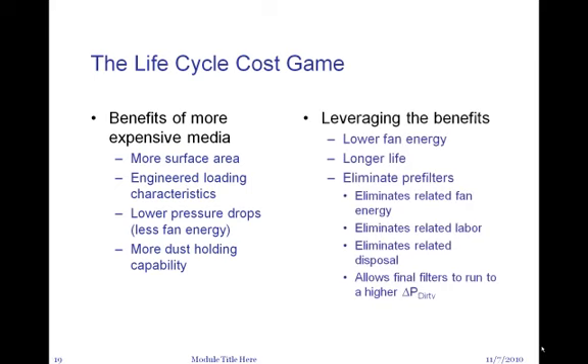It costs you more money, but if you look at it from a life cycle cost standpoint, there can be advantages. There's lower fan energy, there's longer life, so you save on first costs ultimately — even though the filter is more expensive, you buy fewer of them. You may even be able to eliminate pre-filters, which is a huge benefit. Pre-filters don't make the air leaving the final filters any cleaner; they just protect the final filters and keep them from loading as quickly.